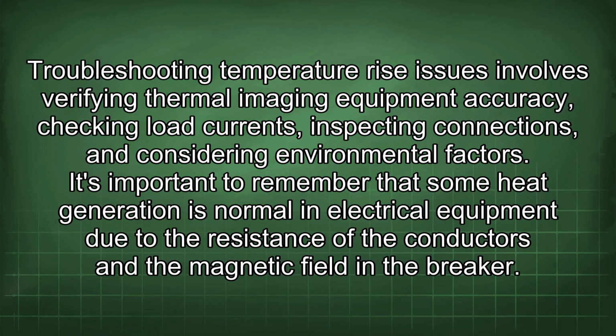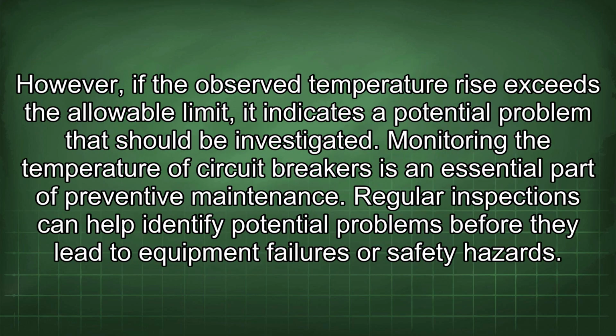It's important to remember that some heat generation is normal in electrical equipment due to the resistance of the conductors and the magnetic field in the breaker. However, if the observed temperature rise exceeds the allowable limit, it indicates a potential problem that should be investigated.